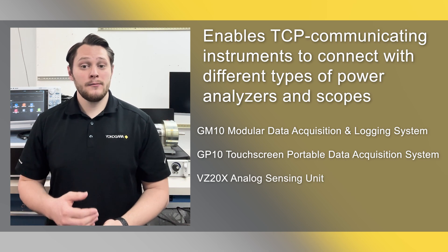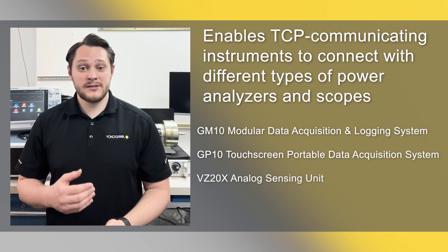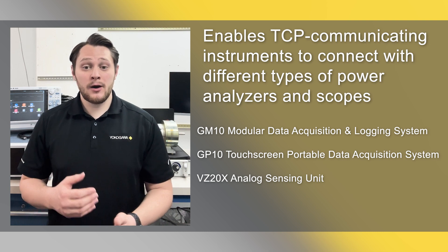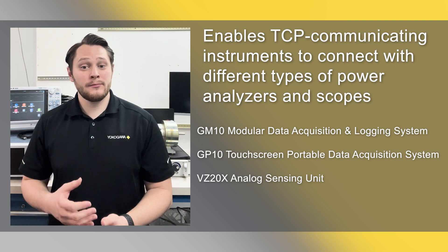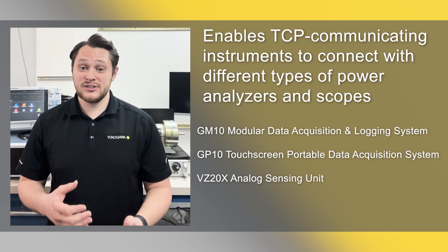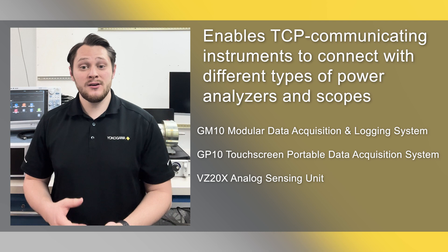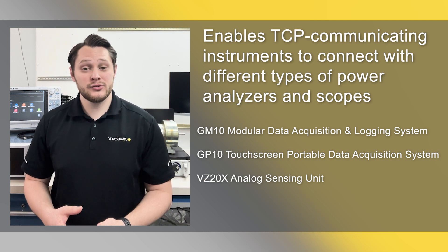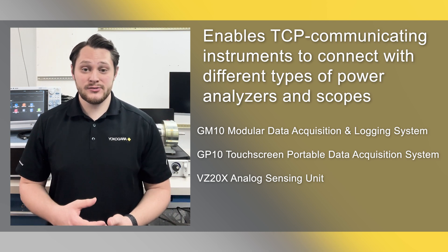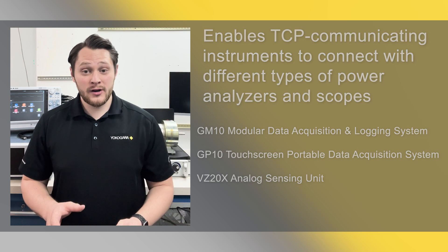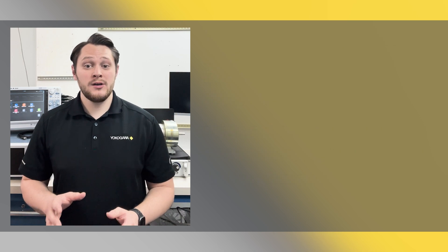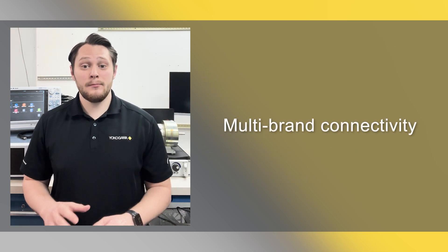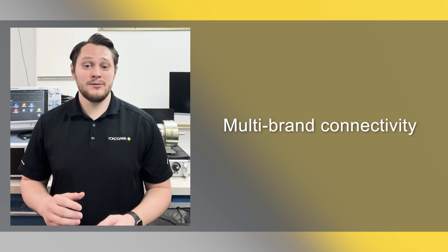These are great multi-channel analog data recorders that sample at a slower speed. We will now be able to combine that data — such as temperature data — with our high-speed voltage and current analysis from our scope recorders or power analyzers. And not just our Yokogawa Modbus TCP instruments; this will connect with any Modbus TCP communicating device.